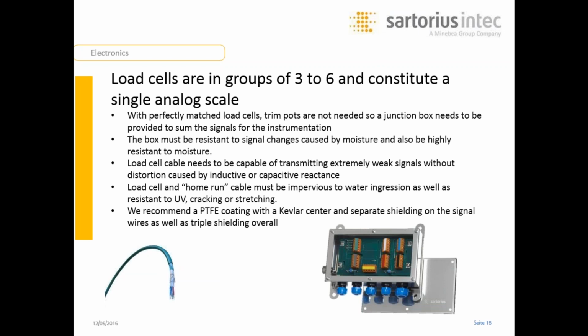Load cells in groups of 3 to 6 constitute a single analog scale. What we mean by that is, with perfectly matched load cells, trim pots are not needed, so a junction box needs to be provided to sum the signals for instrumentation. The box must be resistant to signal changes caused by moisture and also be highly resistant to moisture. Load cell cables need to be capable of transmitting extremely weak signals without distortion caused by inductive or capacitive reactance.